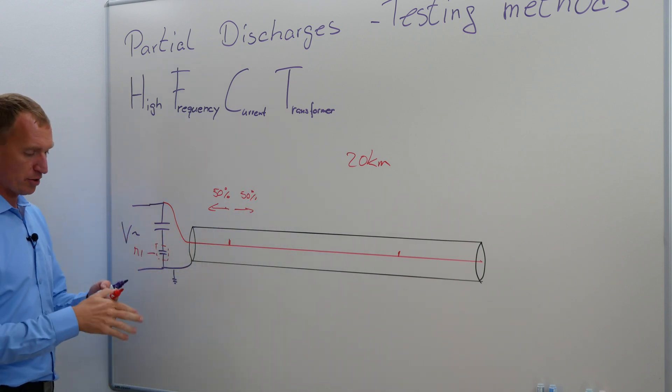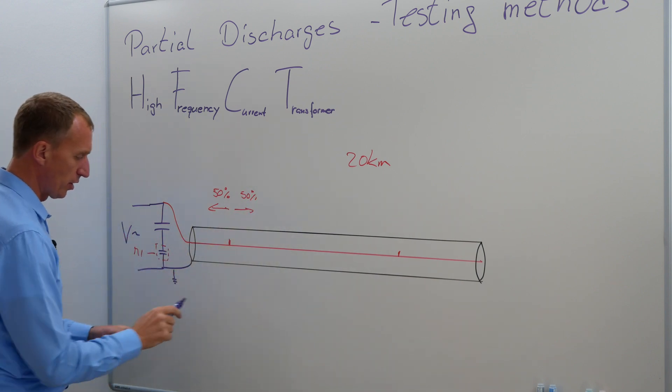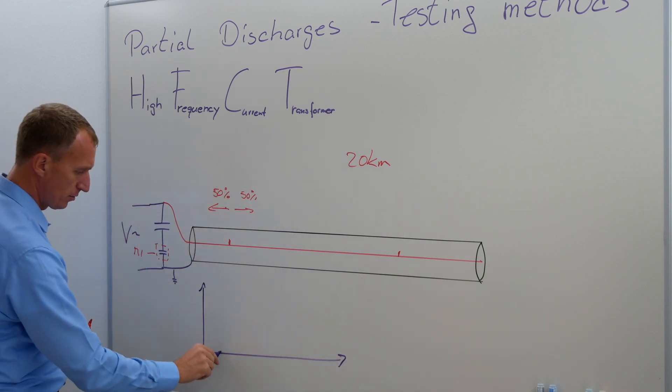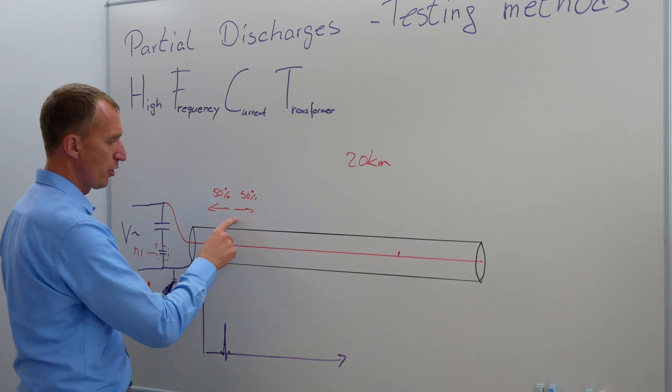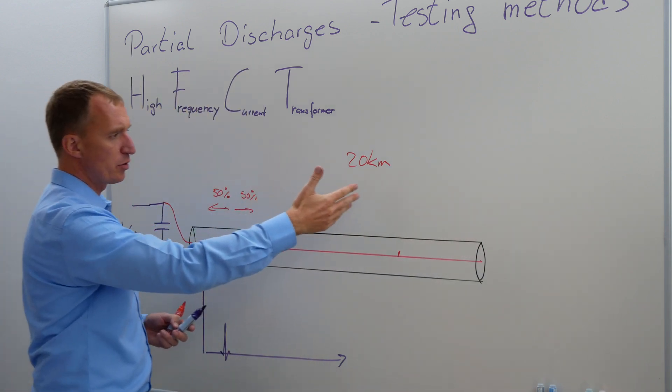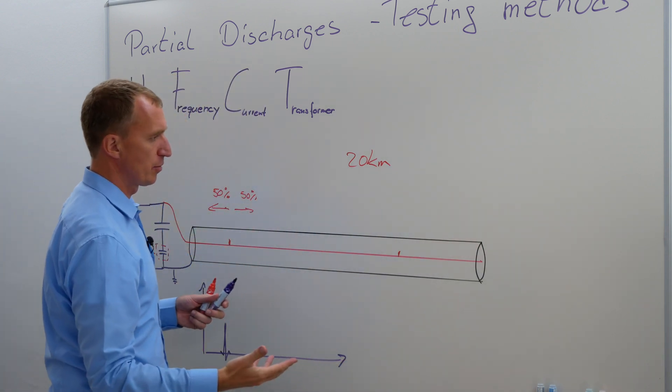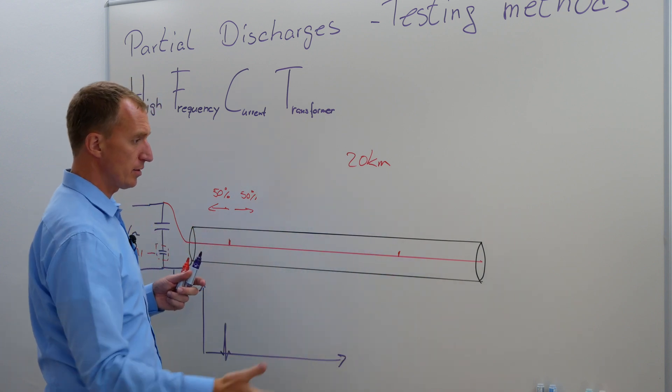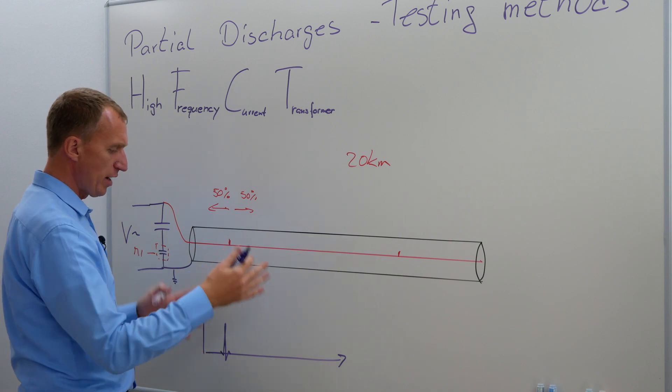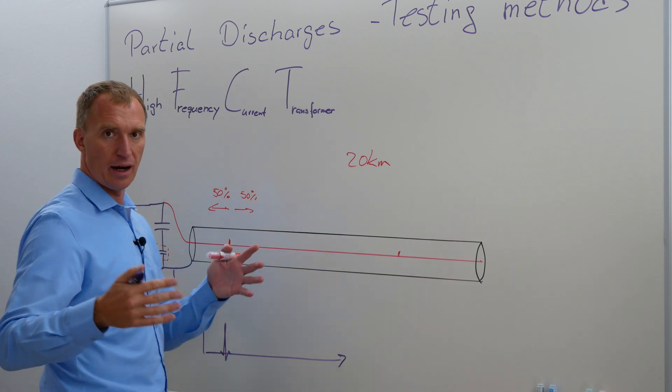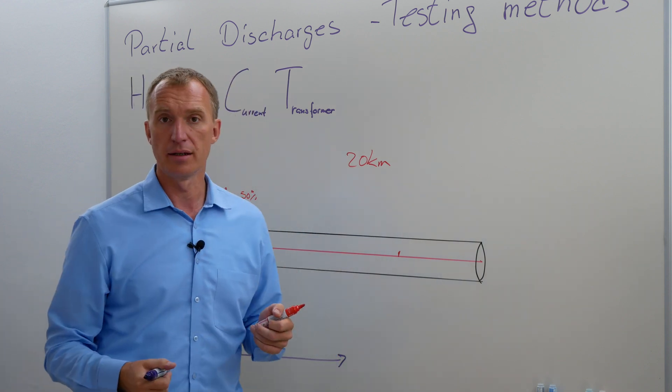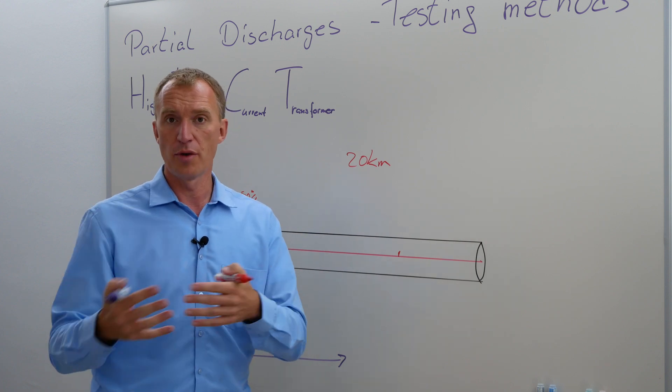Now you realize, I have a partial discharge. We remember we have our TDR. So we're getting our first signal. And now we just say, let's wait. So now this one travels over here and then comes back. If the cable is very, very long, the attenuation is quite hard. And now it takes multiple microseconds for the signal to actually come back. In the meantime, I have seen so many other partial discharges and or noise that I cannot be 100% clear to localize the origin of the partial discharge.